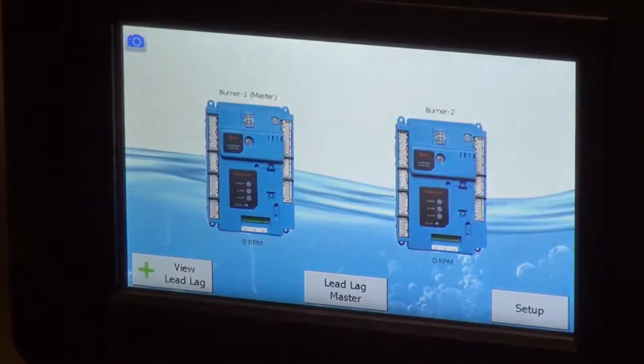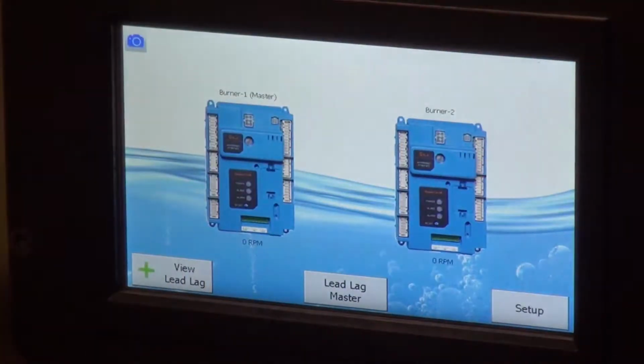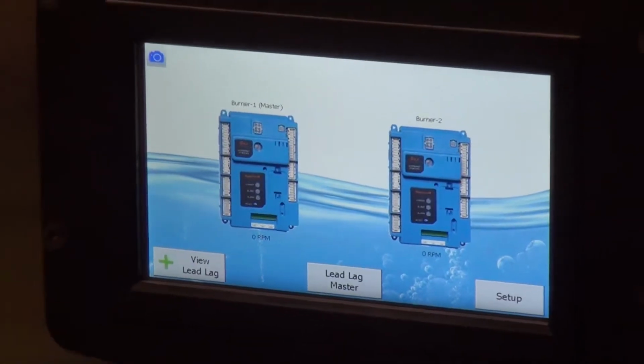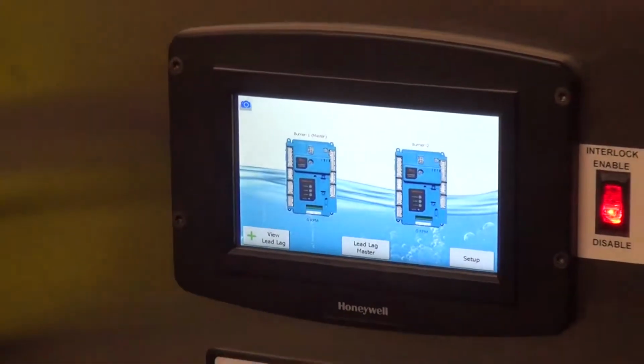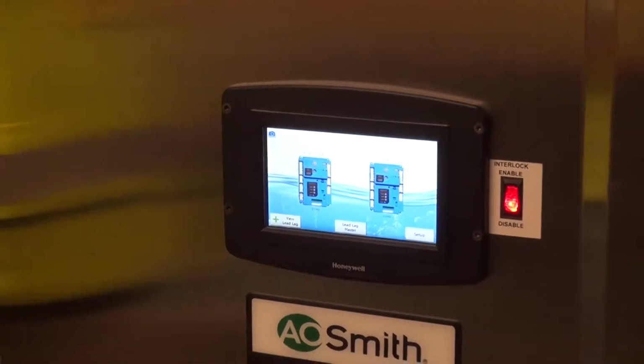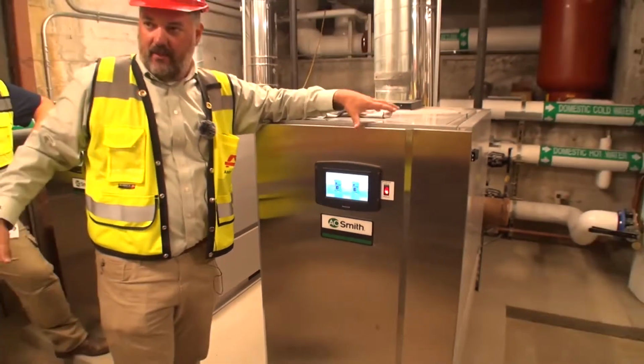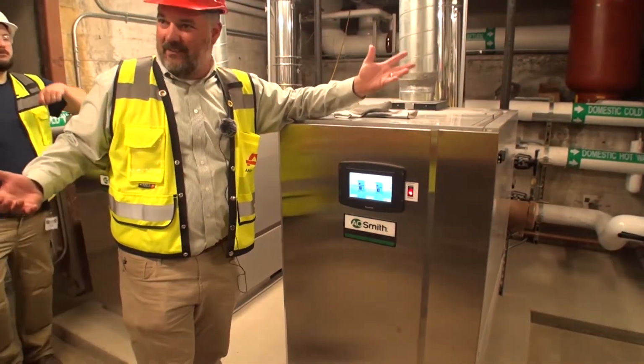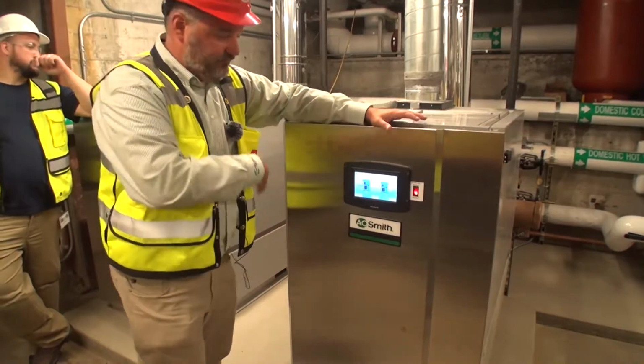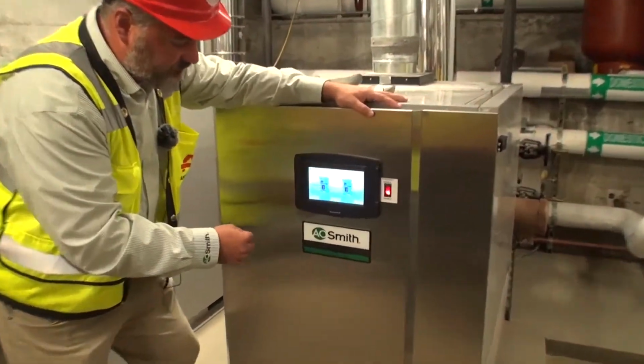Now, the temperature on this unit is 150 and this one's 150. That's going to be relayed over to the Tekmar controller. So the Tekmar controller is not relaying so much this temperature, it's relaying the tank temperature. But the tank temperature is impacted by this temperature. Makes sense somewhat? That's kind of a roundabout way of showing the control.